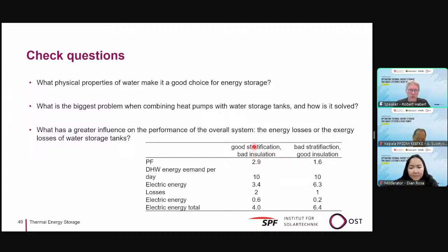If you have good stratification, you have a high COP. To cover the same amount of energy, you only use 3.4 kilowatt hours of electric energy. You have higher losses, and combined with the energy needed to cover those higher losses, you have a total energy demand of 4 kilowatt hours. So the answer is that exergy losses are important, but the best system would have both low exergy losses and low energy losses.